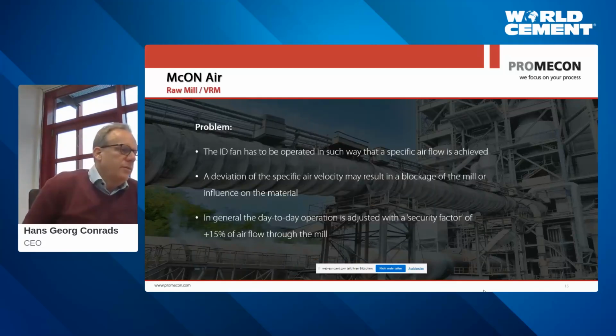Let's look at the problem itself. The raw mill fan has to be operated in such a way that a specific airflow is achieved. And the most important target is to keep the mill running, right? So if the airflow is too low, then you are running the danger that not enough material can pass the classifier, and as a result, the material will get higher and higher on the roller table, and therefore the rollers will basically drown in the material, and that will lead to a trip of the mill.